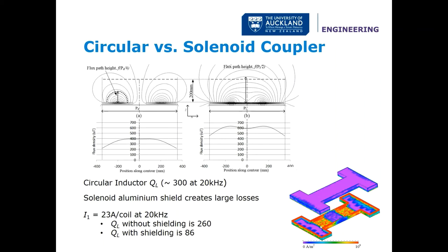The aluminium shield itself will have some loss in it. We can indicate how good the systems are by looking at the quality — reactance over resistance. A typical circular inductor at 20 kHz might have a quality around 300. The solenoidal system without the aluminium shield is close to that, but as soon as we add the shielding, eddy current loss drops the quality significantly — meaning too much loss. Another difference is that while the center fields from the circular are vertical, the center fields from a solenoid are horizontal, giving a different shape of fields at the center of the pads.